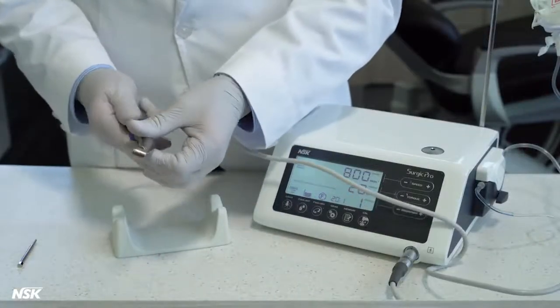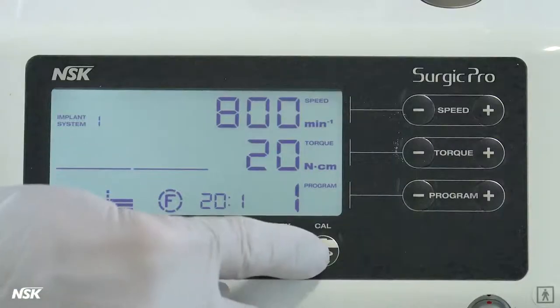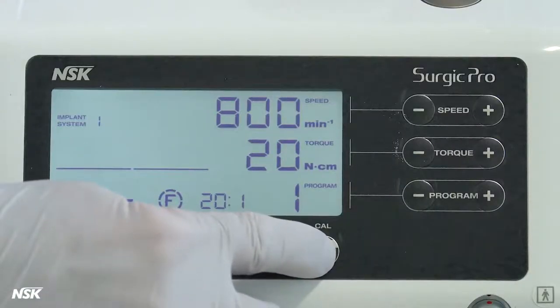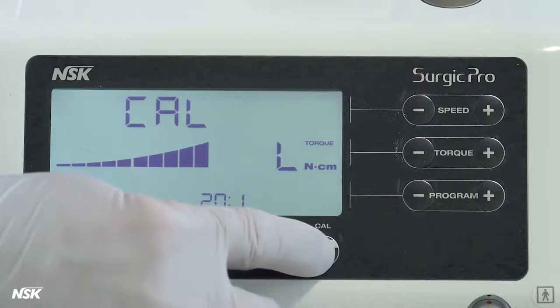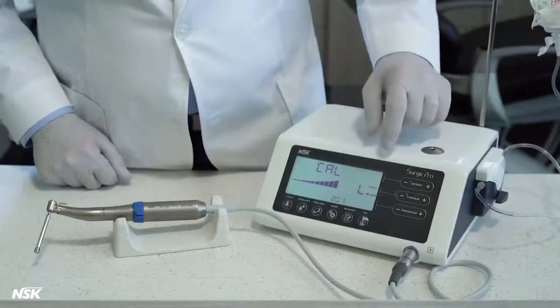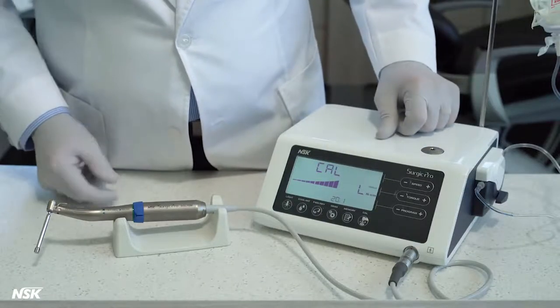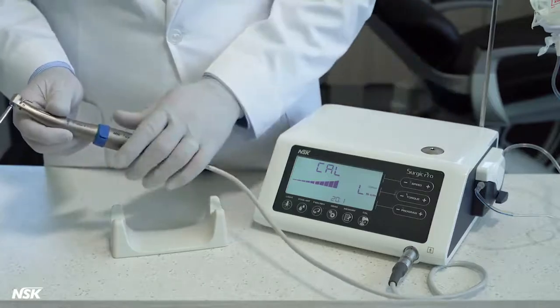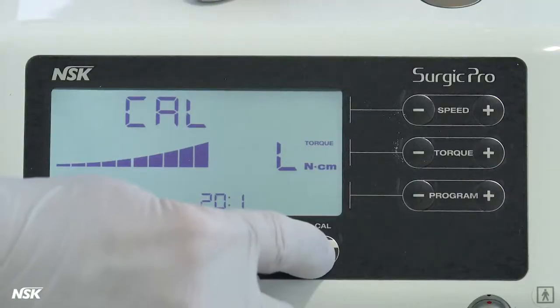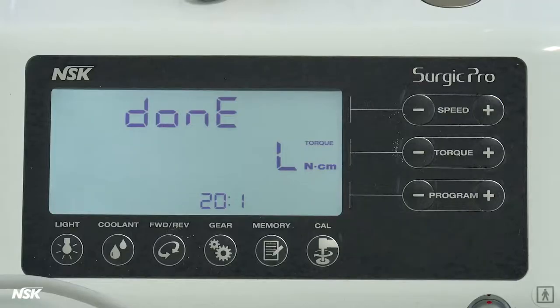Attach the 20 to 1 attachment to the motor and insert the calibration drill. Press the cal key for two seconds. After you hear a long beep, the display will turn to calibration mode. You're ready to calibrate. Step one is no load calibration. Torque displays L. Hold the motor in one hand and press cal key. The drill will begin to rotate. Once this part is completed, you will hear a beep and see done on the display.